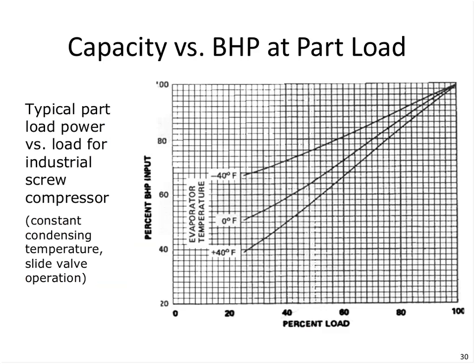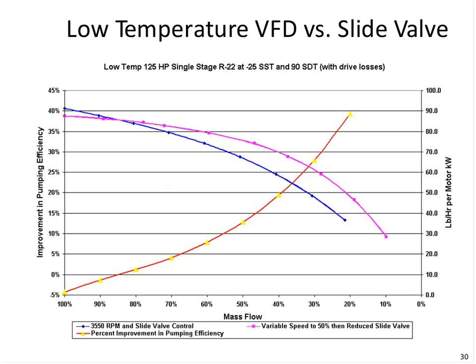Here's an example of a typical energy use at different slide valve positions. So, for example, if we're at 50% load and we're at minus 40 degrees, a typical compressor might use about 70% of the power to deliver 50% of the refrigerant flow. At the same time, if we're at plus 40 degrees, notice the impact of that isn't nearly as much as it is at low temperature. So we do find a more interesting opportunity energy-wise at lower temperatures.